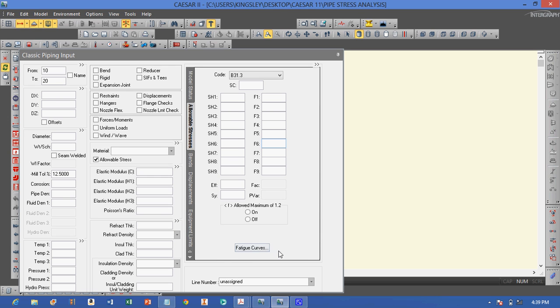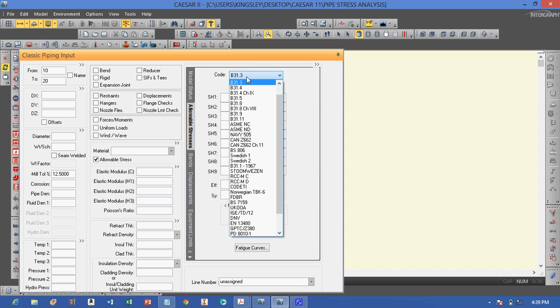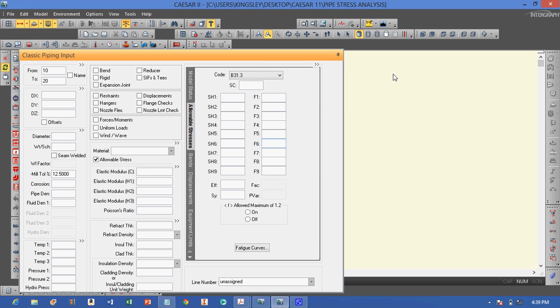CAESAR II is the most popular pipe stress analysis software. It is a system analysis tool to ensure that the piping system is safe. The stresses calculated are code-defined stresses such as B31.3, B31.11, and B31.4. We compare the calculated stress to the defined limiting stress — that is the allowable stress. We make sure that the expansion stress calculated is less than the code-defined allowable stress, that the sustained stress is less than the allowable stress, and likewise that the operating stress is less than the allowable stress.